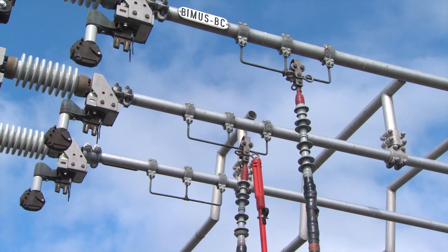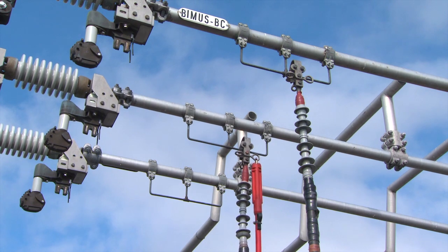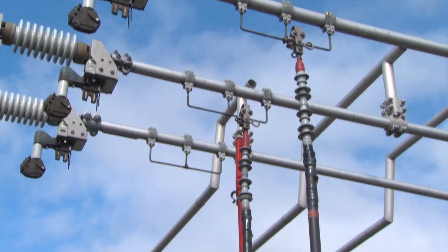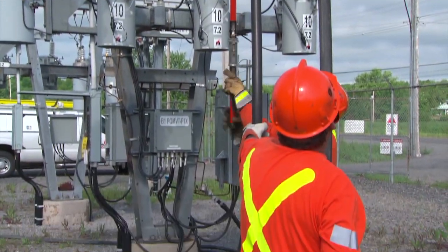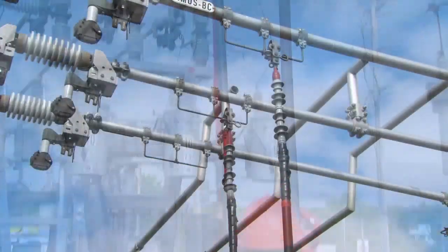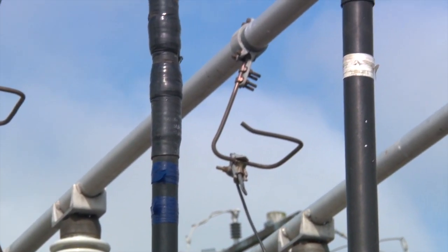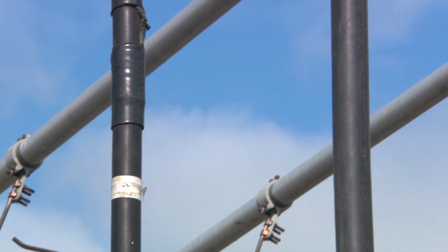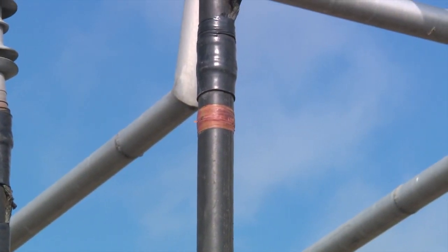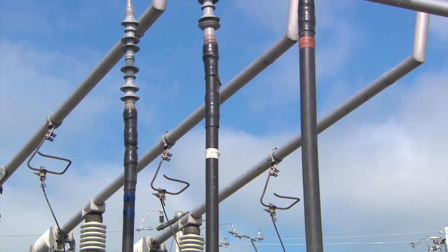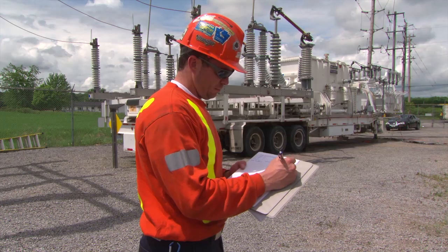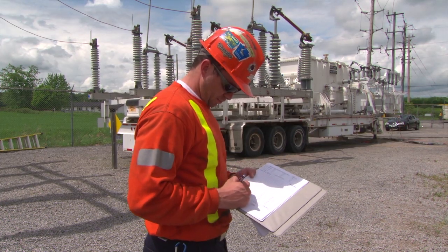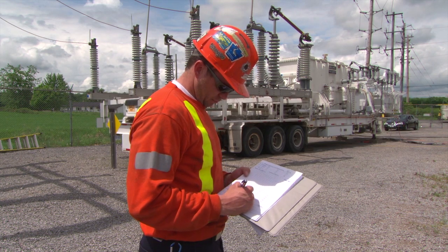If the station has 2 feeders, use the same procedure to install the second set of low-voltage cables. Only 1 neutral cable is used, and only 1 set of cables can be used per MUS recloser. The low-voltage station bus MUS connection stirrups are designed to accommodate 2 cables per phase if required. Each cable is phase marked with colored tape and should correspond with the phase markers on the DS structure. Once all low-voltage cables have been installed, surrender the established work permit.